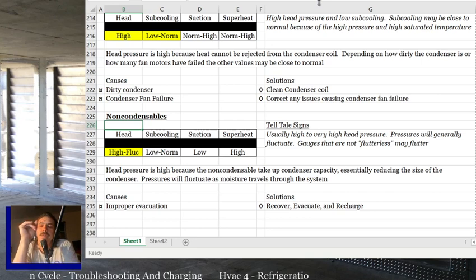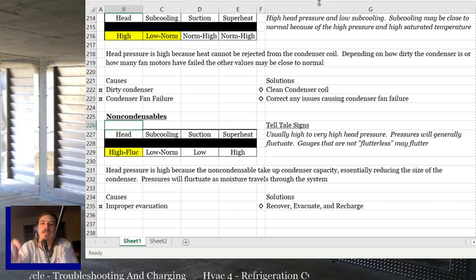So if you just got nitrogen there, it's a non-condensable, but it's not really doing anything but taking up space, which is what nitrogen tends to do. It'll all get trapped in the top of the condenser, and however much nitrogen there is will take up that much space in the condenser. So it basically turns your 3-ton condenser into a 2-ton condenser. Okay, so you end up with a really inefficient system, you turn the 13 SEER system into an 8 or 7 SEER system. So you'll end up with really high head pressures if it's just nitrogen in there and you've got a reasonable amount of refrigerant.